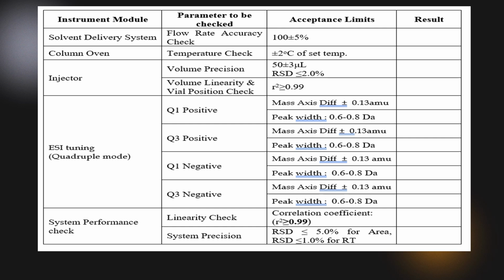Now this system performance check is done by doing a linearity test on the detector and the precision test. Now for linearity, you're going to prepare concentrations like 2 ppb, 5 ppb, 10 ppb, 20 ppb, and when you're injecting these concentrations, it should give you a linear response. So the acceptance criteria of this is more than or equal to 0.99. And for system precision, you're going to inject the same concentration of solution 5 times, and whatever area or response it is giving, the RSD should be less than or equal to 5%, and the RSD of the RT should be less than or equal to 1%. So this is how you're going to calibrate the system performance check.